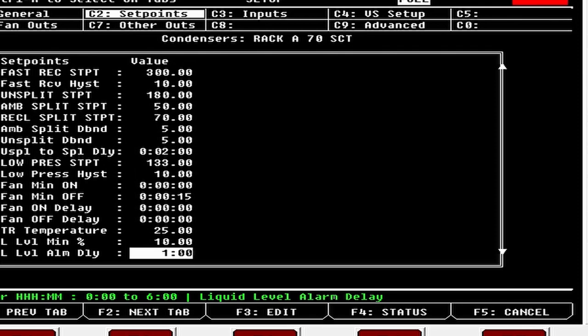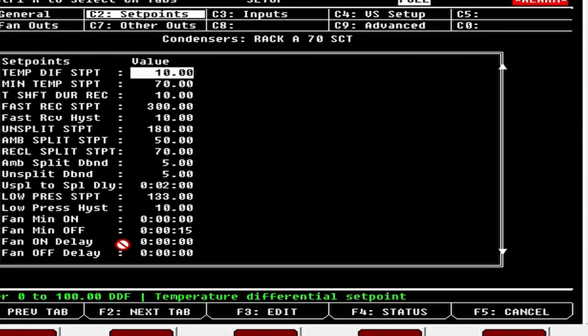Minimum Liquid Percentage: this is where your receiver alarm is going to be if you have it set up in the condenser group. Most customers set it at 10 but I usually go to 15 — I like to know there's a leak earlier. And there's a delay for your low liquid level. That is your Set Points tab — now we're going to head to Inputs.